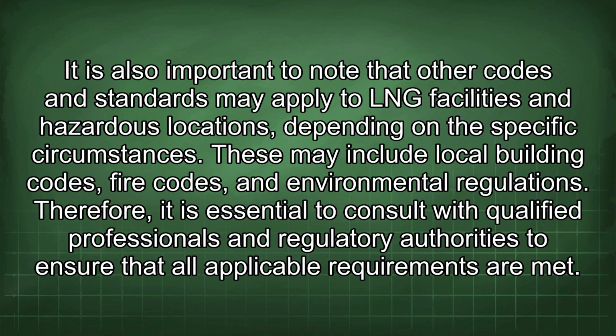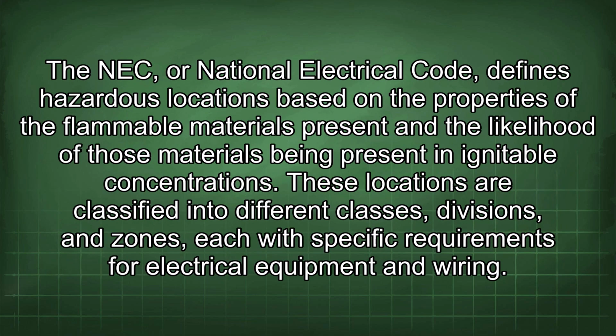It is also important to note that other codes and standards may apply to LNG facilities and hazardous locations depending on the specific circumstances. These may include local building codes, fire codes, and environmental regulations. Therefore, it is essential to consult with qualified professionals and regulatory authorities to ensure that all applicable requirements are met. The NEC, or National Electrical Code, defines hazardous locations based on the properties of the flammable materials present and the likelihood of those materials being present in ignitable concentrations.